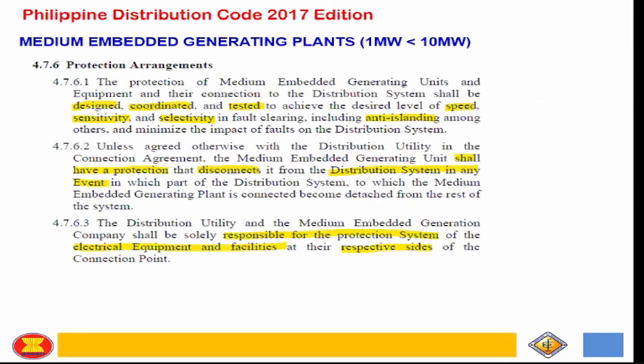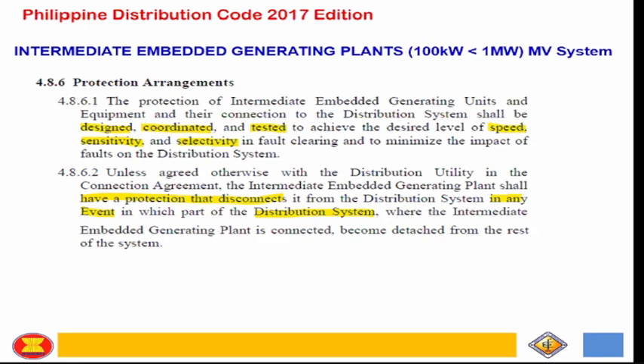And for the medium, anti-islanding is mentioned: selectivity and fault clearing, including anti-islanding, among others, to minimize the impact on the distribution system, and shall have protection that disconnects from the distribution system at any event. So for any event on your side, you are the one responsible for protection, and responsible for the system's electrical facilities and equipment. The speed and the other requirements are the same.